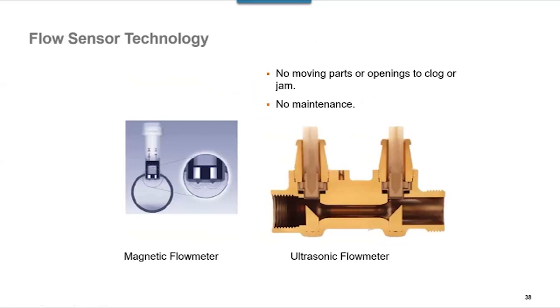One thing I did want to point out, everything we have today is an ultrasonic flow meter. In the beginning, our larger product used a magnetic flow meter, as you see here. Same advantages, same accuracy, 2%, no moving parts. But one thing I do want to point out to you, and we ran across this a few times, flow in this case should go across from one nub to the next, and not, in the case of my picture, hitting directly onto it.